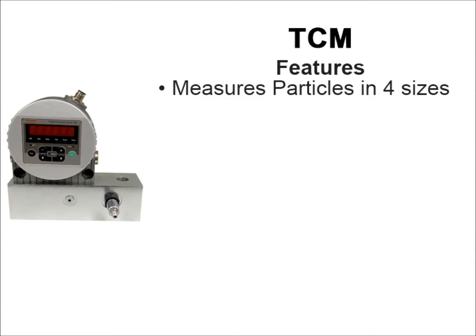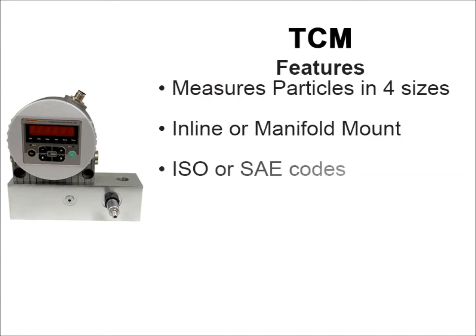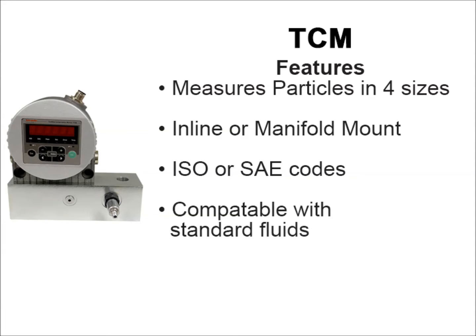The TCM measures particles in four sizes: 4, 6, 14, and 21 microns. The unit can also be used in-line or in a manifold mount if need be. It also measures ISO and SAE codes and gives you a 4 to 20 milliamp analog signal. It's compatible with standard mineral oils and phosphate esters.